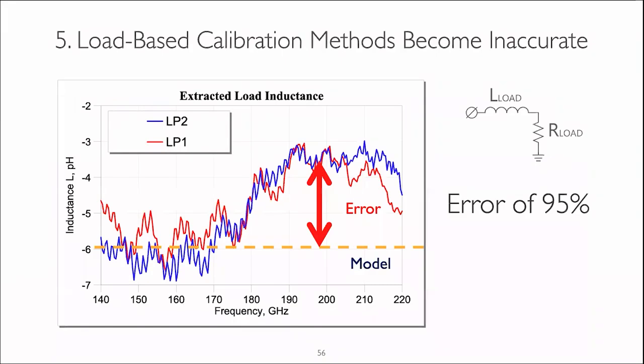This graph shows the result of extracting load inductance out of the planar load, the probe tip load standard, at frequencies beyond 110 GHz. What you can see is that the equivalent inductance of the load is not constant, and it varies from frequency point to frequency point. There are several ranges where it varies really drastically, and we have an error of up to 95%, which means that if we use this standard and this model, we end up with a very large error in our probe tip calibration.